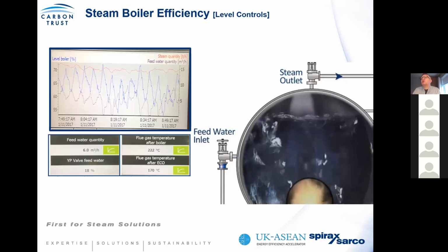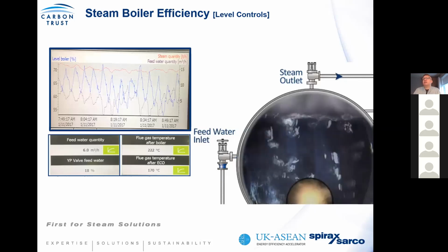So look at your controls. Look at what they're saying to you. For example, this is a representation of a system which employed single level control. What you can see is that the process was very much batch driven, and they found it very difficult to achieve stability in control. And you can see that the level in the boiler, as represented by the blue line, dropped from a range of 55% to 73%.